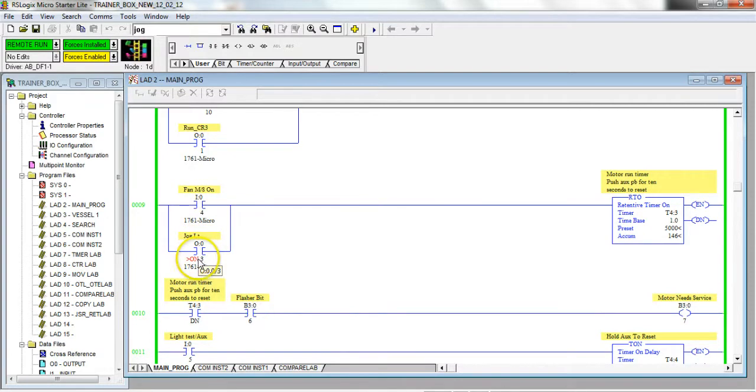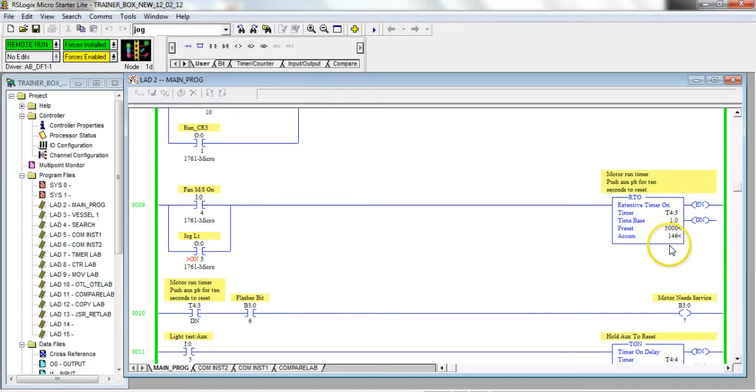You'll see here it tells me that that output address is forced on, but all of its associated bits are not true. It tells me it's on, but as you can see it's not true because this timer is not timing right now.